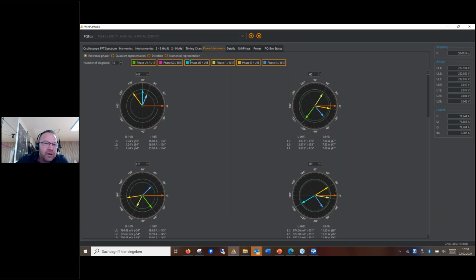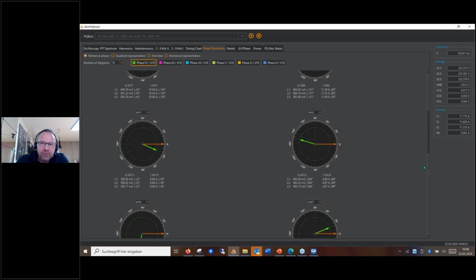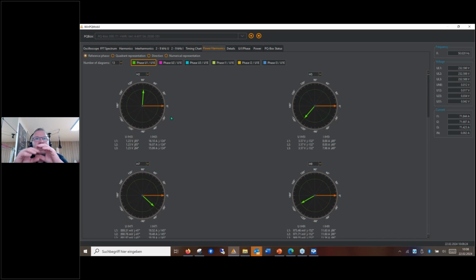direction of the harmonics. First, I only select phase L1. So here we have the basis. Orange means this is the fundamental of the calculation. This is 0. And we see the third harmonic, the fifth harmonic, the seventh harmonic, the ninth harmonic. So all the harmonics coming here. We see the interference in the grid at the moment. So I choose the fifth harmonic, 3.59 volts with a phase angle.